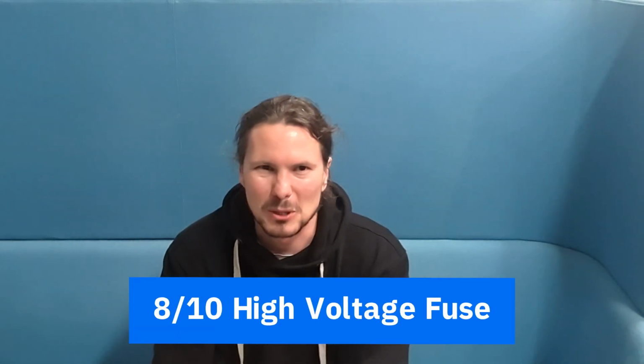Number 8, the high voltage fuse. There's an important misconception here. The high voltage fuse is not going to save you when you touch the high voltage contacts. It's not going to pop. It will only pop after hundreds of amps flow through it for seconds, minutes even. Unfortunately, any human or animal that touches it would be long dead or severely damaged by that point.